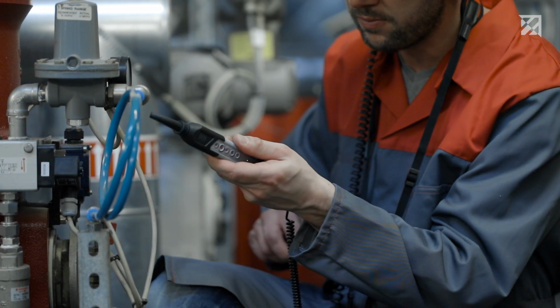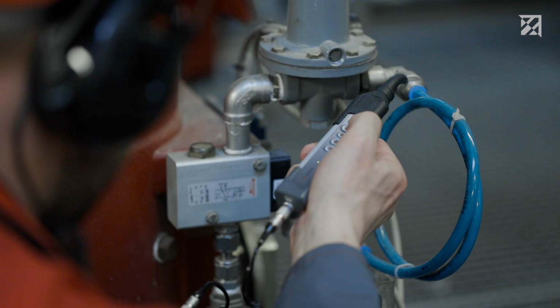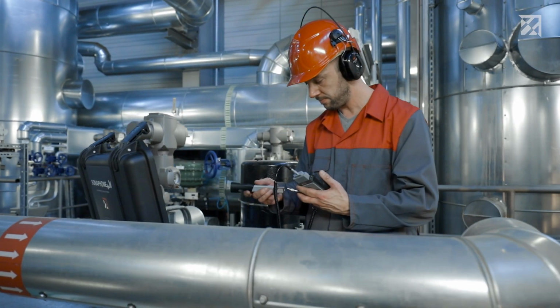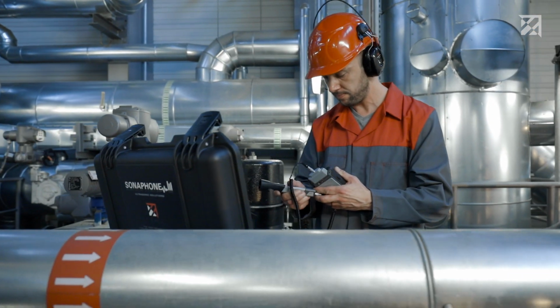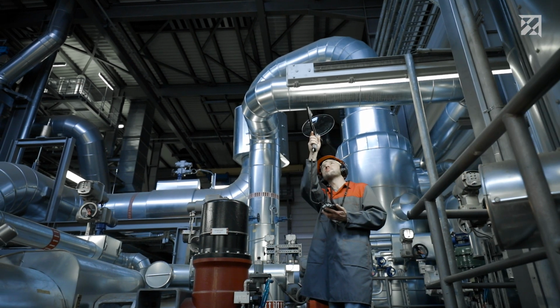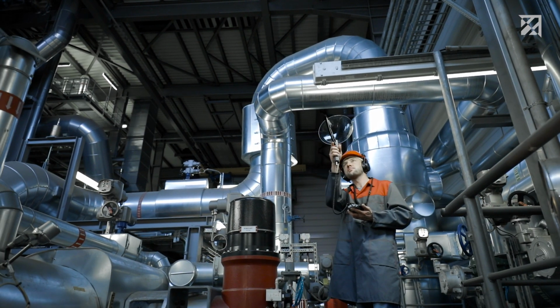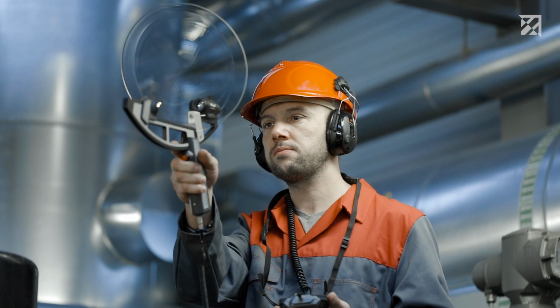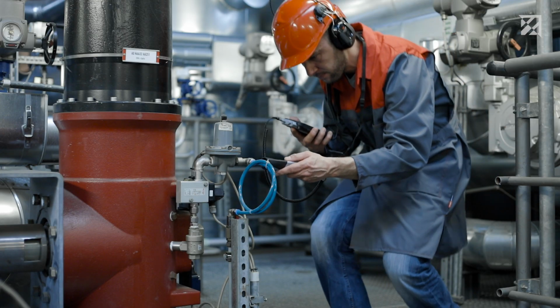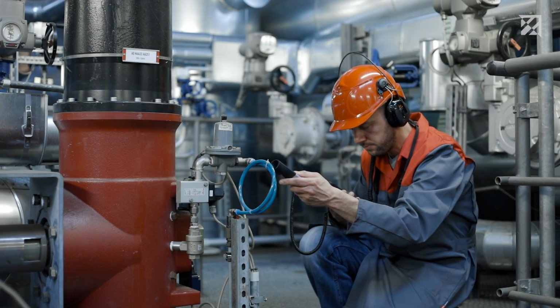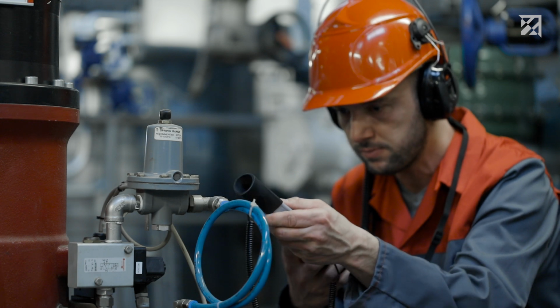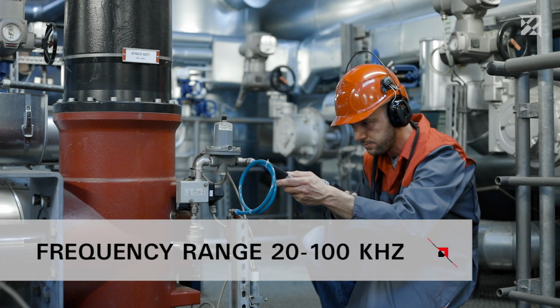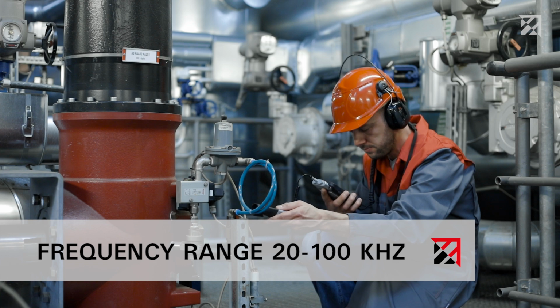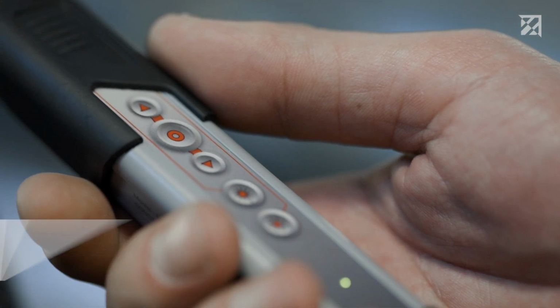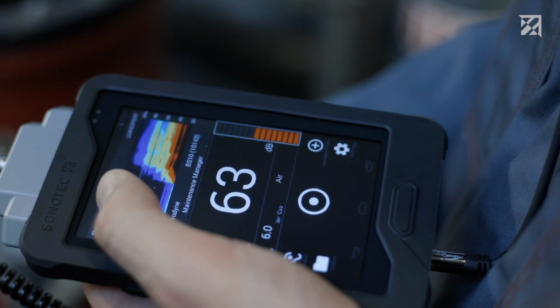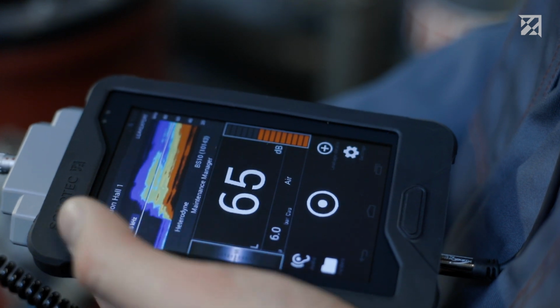The SONAPHONE with innovative airborne sound sensor makes it possible. Just put on the headphones, start the app, and get searching. The parabolic sensor BS30 can be used for leak detection over large distances. For short distances, the airborne sound sensor BS10 is used. An extremely wide range of different leak types can be detected thanks to the broadband microphone with a working range of 20 to 100 kHz. And any background noise in the audible range can be suppressed.